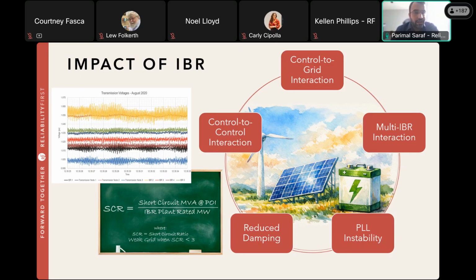So under certain conditions, if these controllers, that is the plant-wide controller and these local controllers, are not tuned properly, they can have interactions with each other, and that can result in oscillations. So a single IBR plant can demonstrate something known as control to control interactions, where different controllers that operate on different time scales can interact if not properly tuned and trigger oscillations.